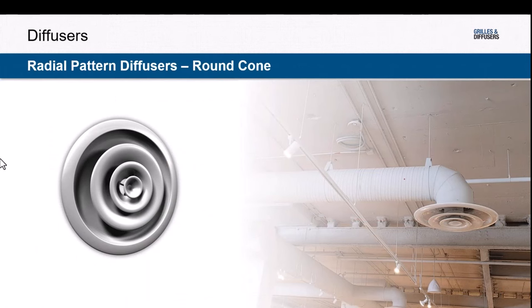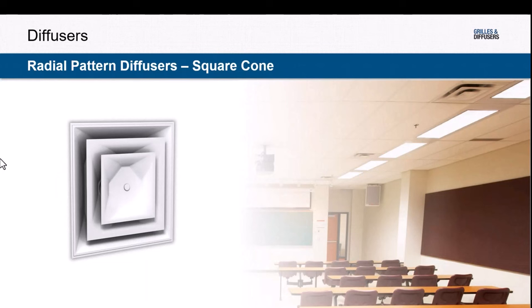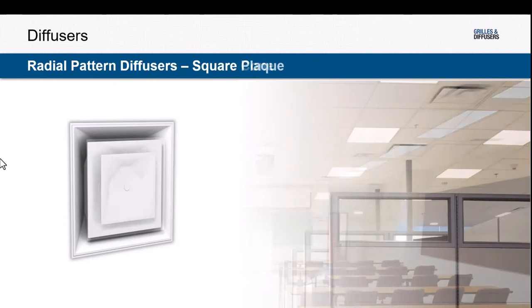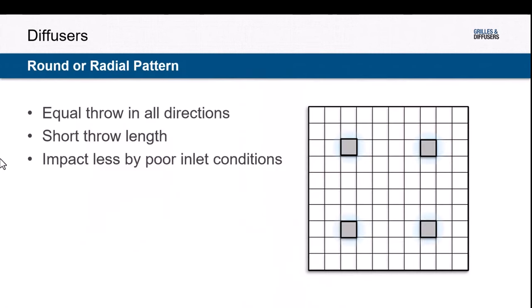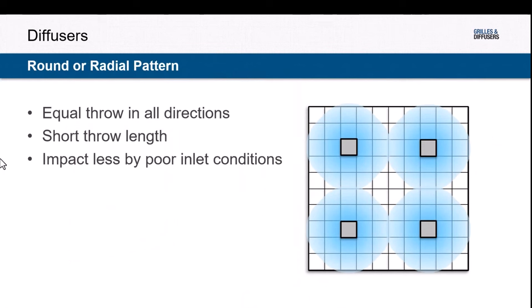Looking at radial pattern diffusers — whether a round cone, square cone, or square plaque diffuser, all quite common air outlet types — these all have radial patterns that move equally out away from the diffuser in all directions. Because the air moves in all directions, throw length is typically shorter. A nice feature of these radial pattern diffusers is they are typically impacted less by poor inlet conditions.